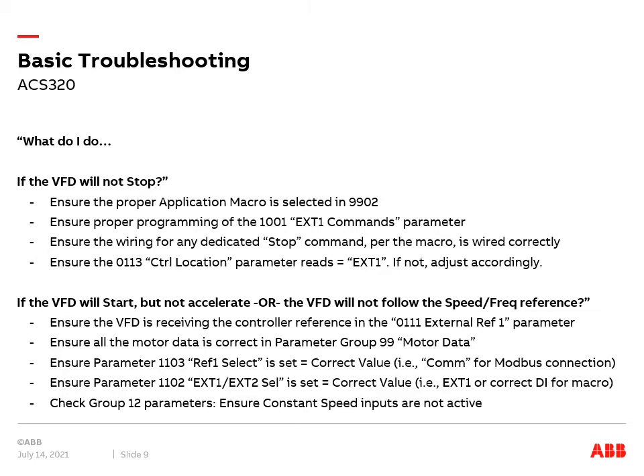Ensure parameter 1102, which is ext1/ext2 selection, is set equal to the correct value — for example, ext1 or the correct digital input for your given macro. And lastly, check group 12 parameters and ensure that constant speed inputs are not active.